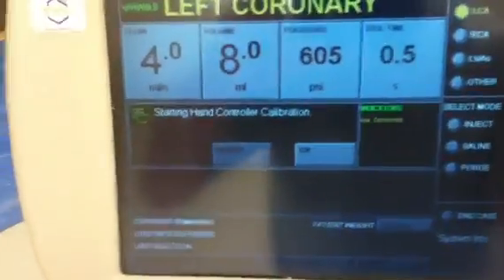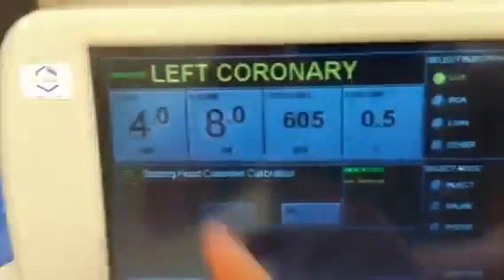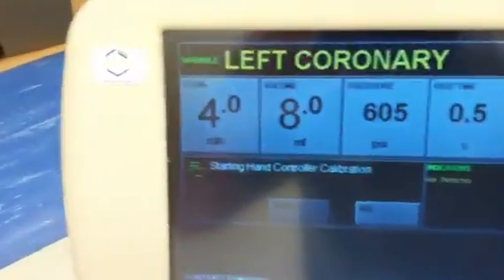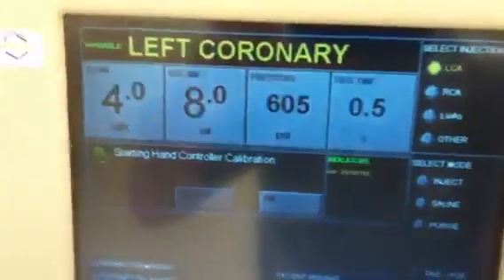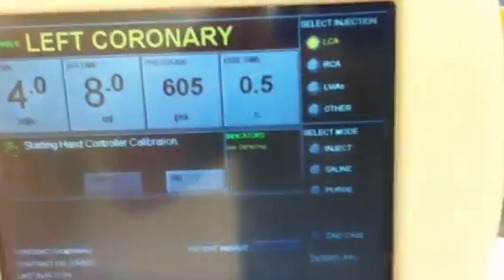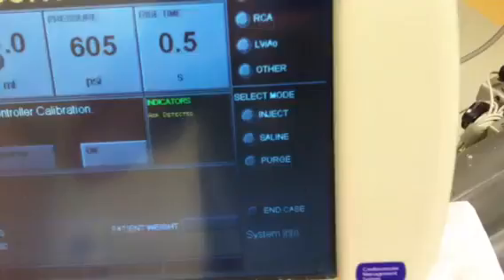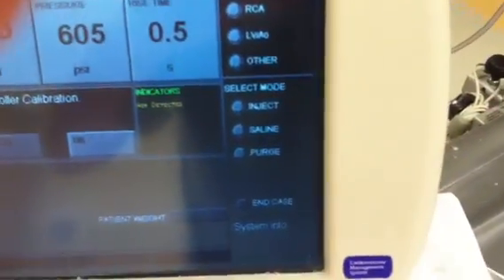Once you're done with this, here's your screen that you go through. You basically just go through all that. You hit your hand calibration. This is where you set what your flow rate is for each injection. This is your pressure, which normally will be preset, so you don't have to deal with that, nor do you really have to deal with your rise time. You have your inject, you have saline and purge, and we'll probably cover that in a later class.